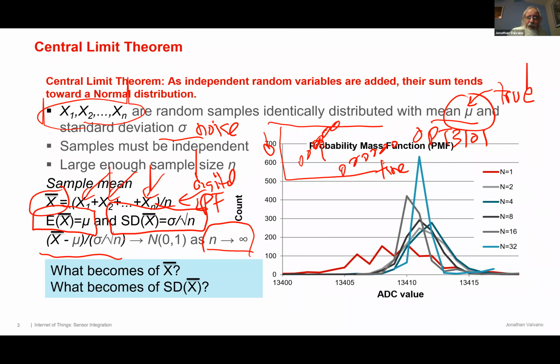So this plot is a probability mass function, which means a constant voltage was put into the A to D converter and measured 1,000 times, and this one here was with no digital filter. This is with a 2-point average, 4-point average, 8-point average, 32-point average, and the take home of this is the standard deviation gets small. Okay. The standard deviation gets small. And the central limit theorem just goes normal, right? The red one clearly isn't normal. The gray one isn't normal, but as n goes large.